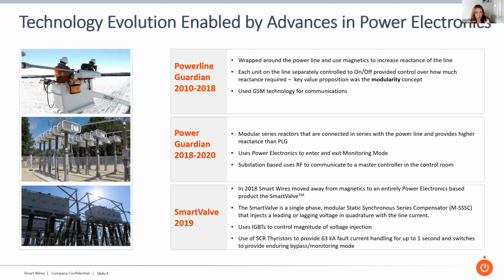And that's when we started to invest in moving over to an entirely power electronics based power flow control technology. And we resurrected a technology that had been first investigated on power systems in the 80s called static synchronous series compensator. A bit of a mouthful, so we always just call that a SSSC technology. And we made a significant number of changes to that technology, taking advantage of changes in the capability of power electronics over the decades. And we now have a world-leading product of modular SSSC technology deployed on grids around the world. And that picture there is from National Grid, where the technology is installed at 275 kV and 400 kV. And of course, in fact, exactly the same equipment is also installed at 330 kV. Our installations at the moment, the highest voltage we're at is 400 kV. We have a 500 kV installation in South America next year.